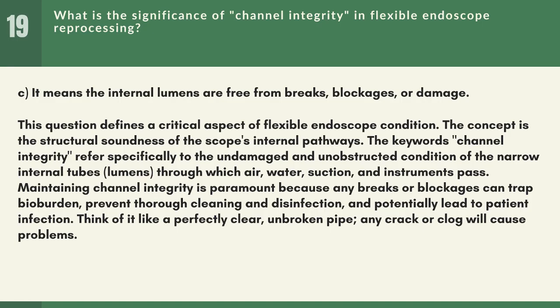This question defines a critical aspect of flexible endoscope condition. The concept is the structural soundness of the scope's internal pathways. The keywords "channel integrity" refer specifically to the undamaged and unobstructed condition of the narrow internal tubes, lumens, through which air, water, suction, and instruments pass. Maintaining channel integrity is paramount because any breaks or blockages can trap bioburden, prevent thorough cleaning and disinfection, and potentially lead to patient infection. Think of it like a perfectly clear, unbroken pipe. Any crack or clog will cause problems.